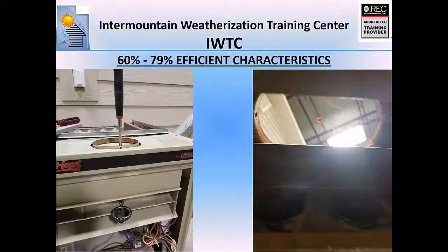If the CAZ is under extreme depressurization, or something's blocking this flue, or the flue's designed poorly, those flue gases, instead of going up and out that hole, will just spill out into the room, right through this guy. And it's pretty easy to tell if they've been spilling. You'll start to see black buildup, rust and things, just like you do on the top of a water heater that's spilling. That's one of the things you can visually look for to help you determine what kind of furnace it is or what efficiency it falls into.